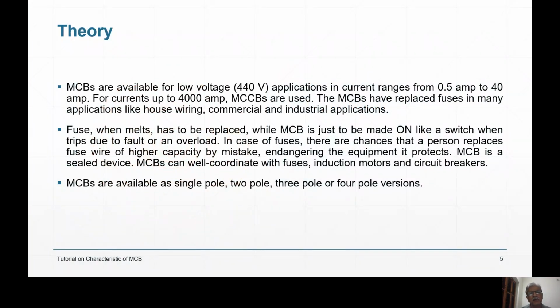MCB is a low voltage device. Up to 440 volt it is available. The current range in which the MCB is available is 0.5 ampere to 40 ampere. That is, MCB rated for as low as 0.5 ampere is available, and up to 40 ampere full rated current. That is full time, 100%. 24 hours and 365 days, you can pass 40 amperes through that. But for currents like 2000 ampere, 3000 ampere, MCB cannot be used. There people are using MCCBs, molded case circuit breakers. The principle of both MCB and MCCB is more or less the same. Only the current range is different.